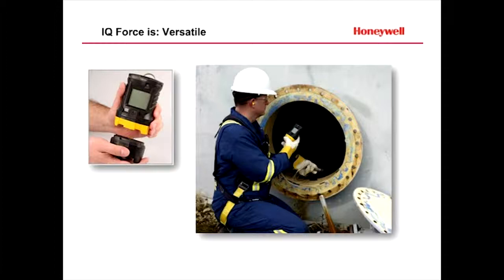The IQ Force Diaphragm Pump attaches to the instrument with one thumb screw. It's powered by the instrument with an internal pressure sensor to reliably detect blocked flow without any false blocked alarms. This diaphragm pump is similar to what we used in the Gas Alert Max XT, so if you're familiar with how robust that system is, you can expect the same performance here. When the pump is installed, the instrument still runs 14 hours.